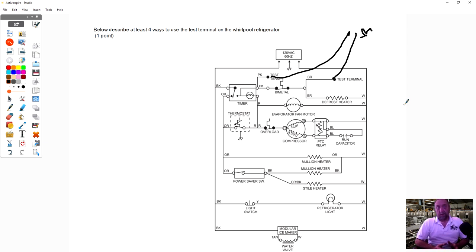So what are the things that we can test? I can check with ohms my defrost heater. If I go brown on that plug and use the neutral on the light bulb like I told you, then I could check the defrost heater for continuity and see if the defrost heater is good right from that test plug.